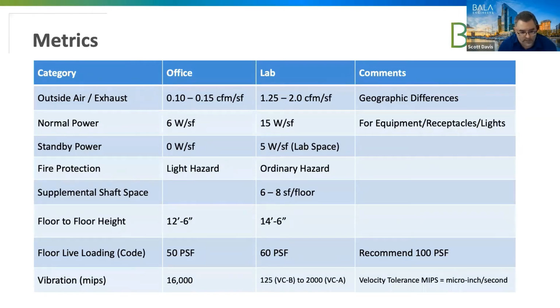Another avenue might be to develop what I'll call horizontal mechanical spaces. Essentially they may run parallel to the labs, and within these spaces we route the electrical conduit, the mechanical piping, the plumbing process piping such as compressed air and lab vac, and you'd also have your VAV boxes located so that you're minimizing the amount of ductwork that you actually put into the ceiling cavity to just really be the branch runouts to your diffusers.